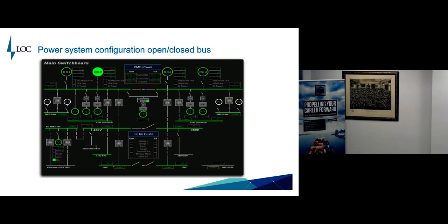will create a voltage dip across the whole bus, and then the protection system will open the bus tie within a certain period. But before that, there is a voltage dip on the main bus. Those voltage dips will affect these running thrusters. So they have to have this voltage dip ride-through capability during the zero volt. All this equipment should be running.